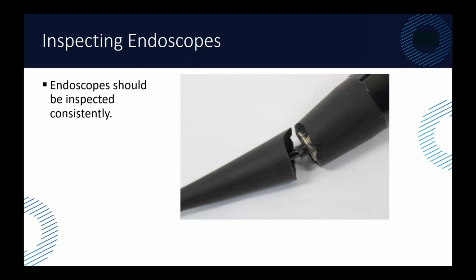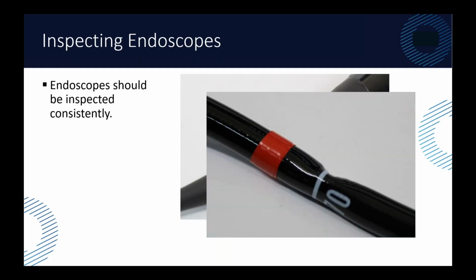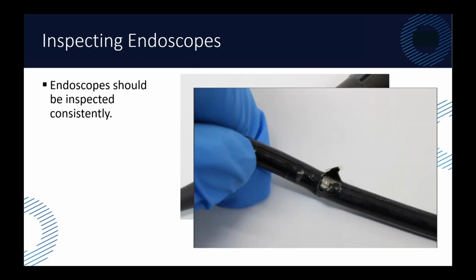And the smaller the problem you fix, generally the more likelihood that it's going to work, and it's going to be a lot cheaper. So if we've had people say, oh, well, my probe's starting to do that, I think I'll just wait for it to get worse. Why? The only time you do that is if the probe is not repairable. Like, nobody repairs that probe. Okay, you might as well just use it until it dies. That's a fair statement. Until you check in, make sure that's real. Don't do that. This is an example of an insertion tube that somebody got a molar on it. I can't tell you if that's an ultrasound or an endoscope. This is an insertion tube that something happened to. I can't really tell what got it, but that took significant force. And that almost looks like something fell on it, or that's probably not caused by a patient. It's probably caused by improper handling somewhere along the way.